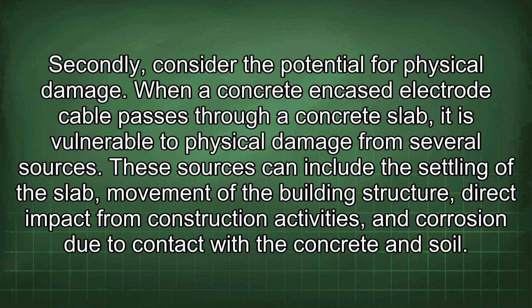Secondly, consider the potential for physical damage. When a concrete encased electrode cable passes through a concrete slab, it is vulnerable to physical damage from several sources. These sources can include the settling of the slab, movement of the building structure, direct impact from construction activities, and corrosion due to contact with the concrete and soil.